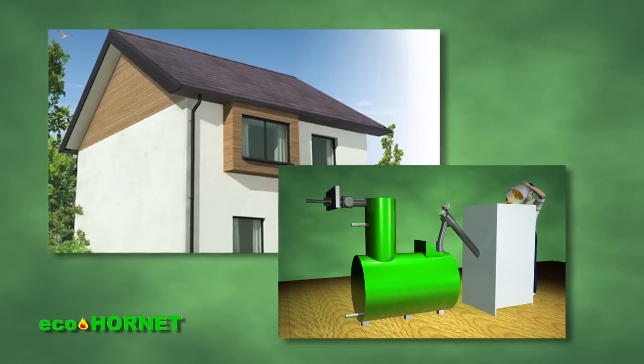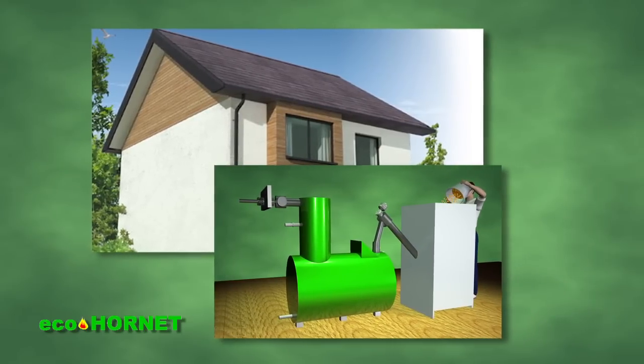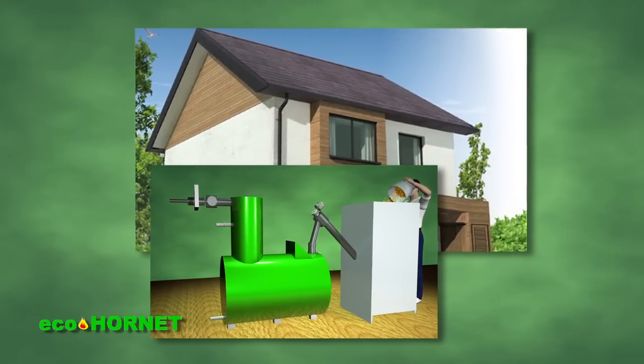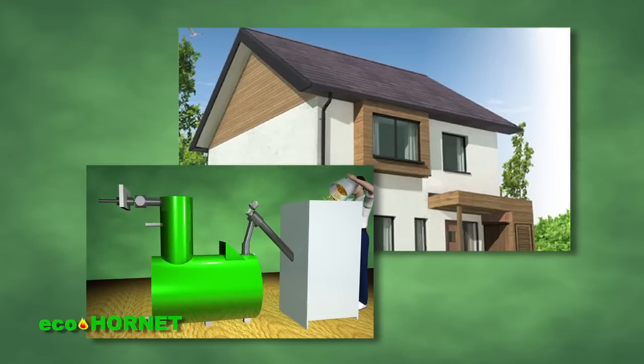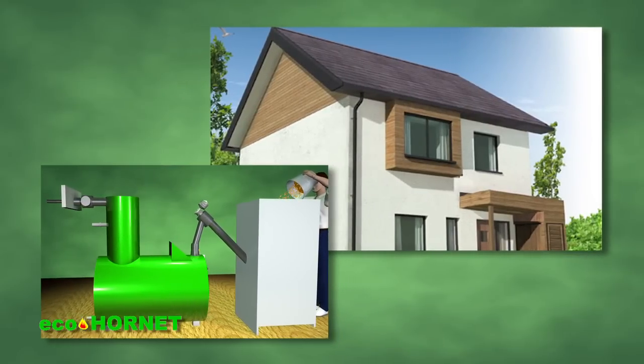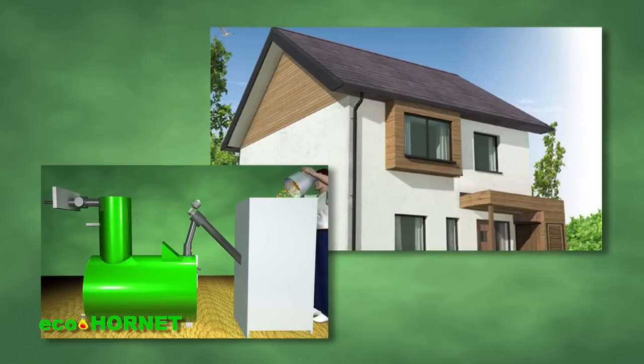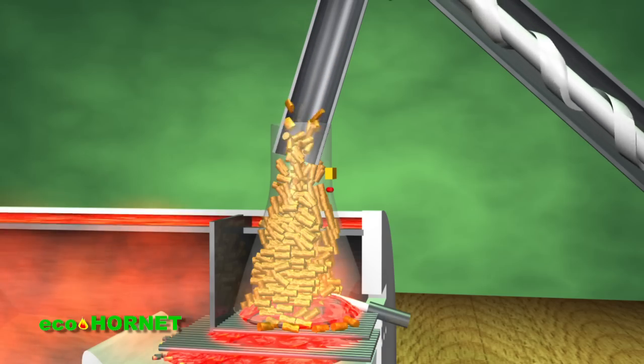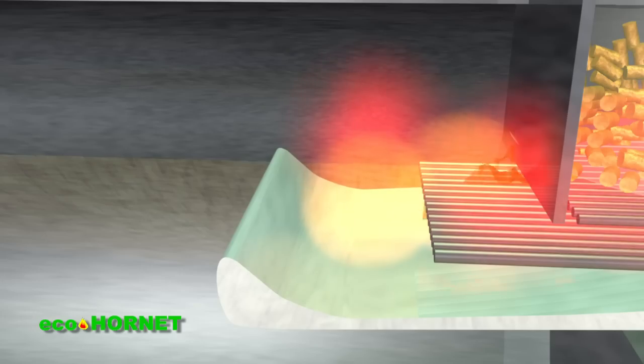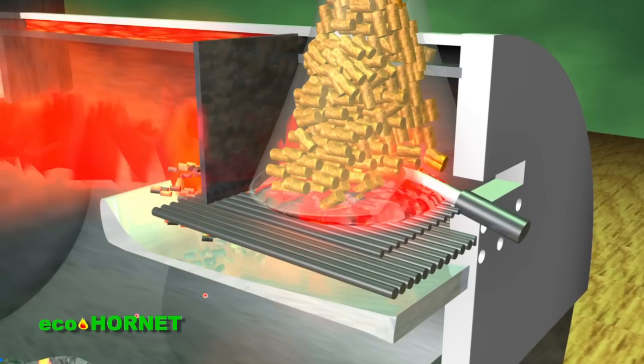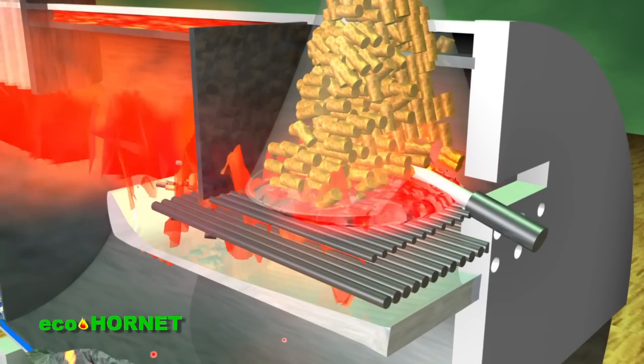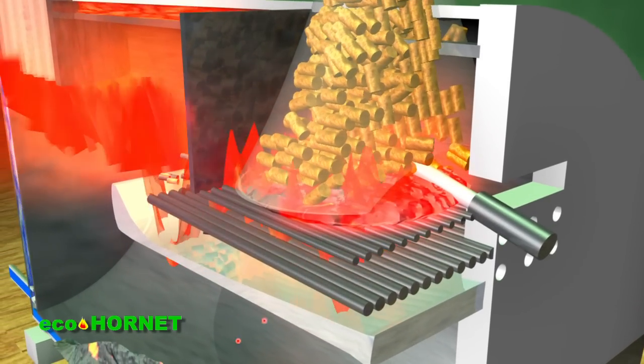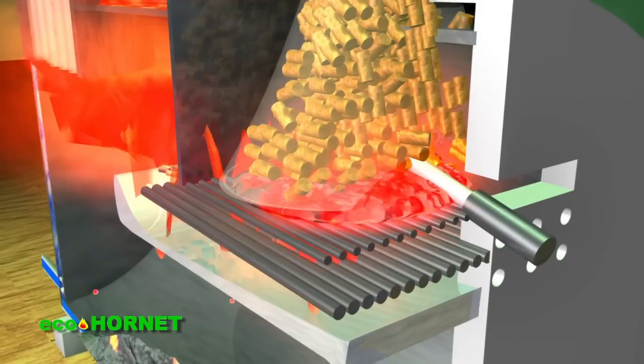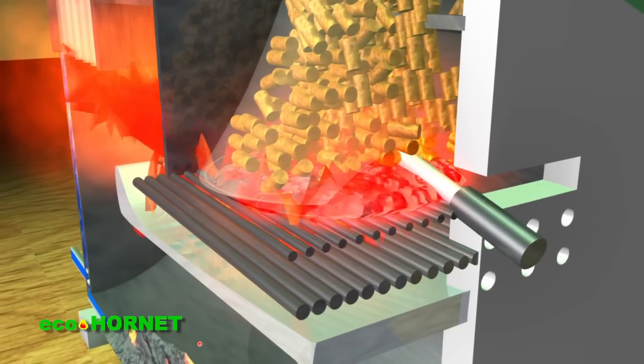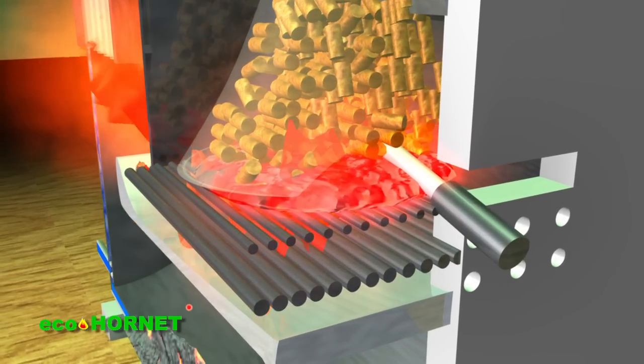The combustion process continues until the room thermostat, which is part of the automation system, gives the command to stop the heating system, when the space where it has been placed has reached the desired temperature. The resupply of the combustion chamber with pellets is performed several times until the ambient thermostat registers that the set temperature has been reached and stops the pellet resupply. The pellets in the burner are ignited and burned completely, and the burning stops until a new supply and ignition command is given by the ambient thermostat.